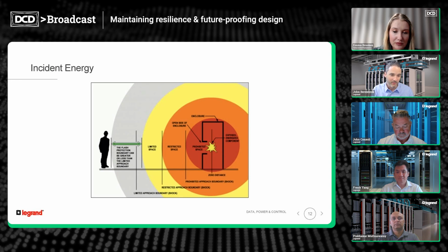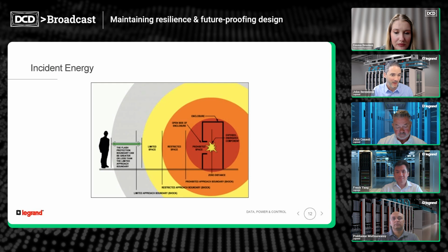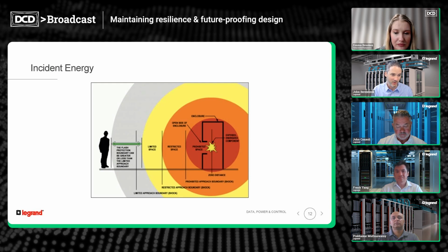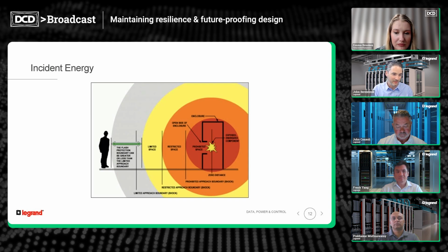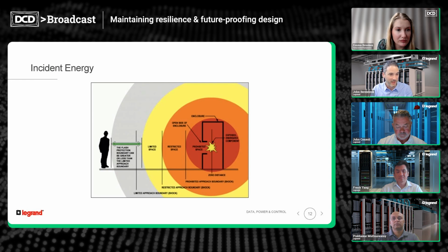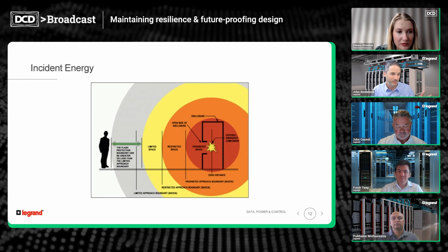What we've tried to do is address that through fusing. Fusing can reduce the fault clearing time, and if the fault clears quicker, it's a much safer solution. Our PDUs can withstand 10 kA, and we can get a 65 kA fault current down to 10 kA or below pretty easily by adding fuses to our tap-off units from our power rails.